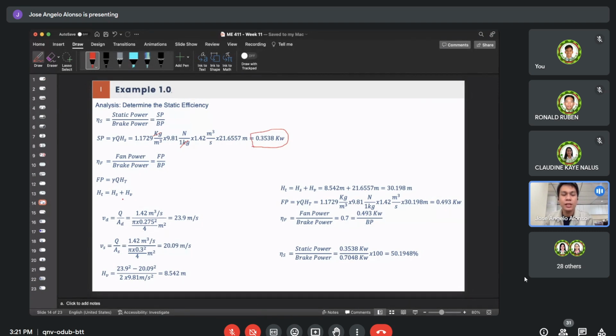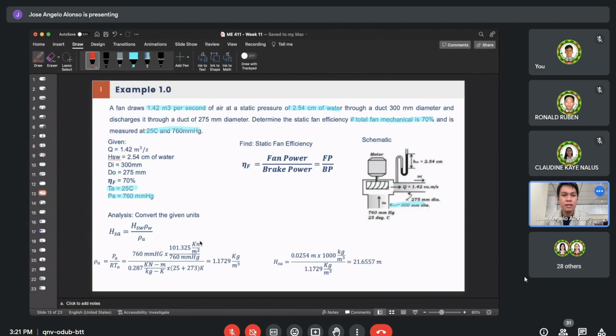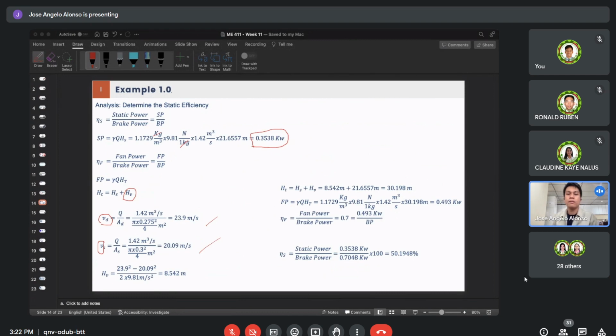Next, determine naman the velocity head by determining first ang value ng velocity ng discharge and velocity ng suction. The problem gave us already ang diameter ng inlet o suction, diameter ng outlet o discharge, and the volume flow rate, which is 1.42 cubic meters per second. So makakalkula natin ang velocity ng discharge and velocity ng suction. Remember Q equals AV, so V equals Q over area, which is pi d squared over 4. So we have here the values ng suction and values ng ating discharge.